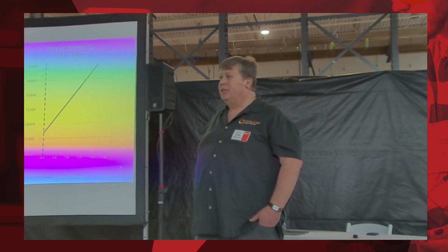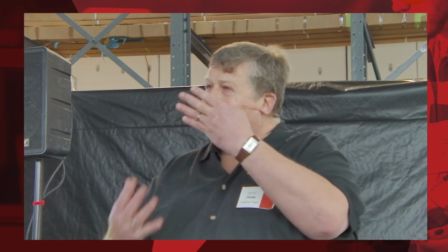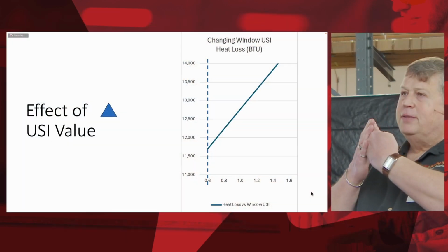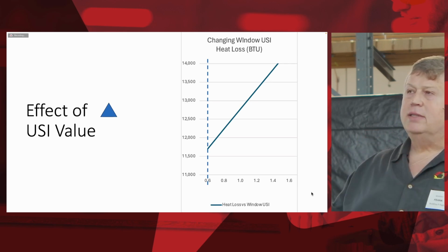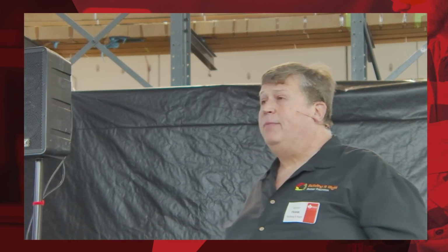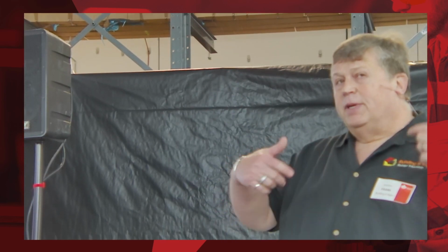But now you got a less efficient device that's using more energy to be less efficient. And you got more mechanicals. You got a little squirrel cage or something running with a desiccant, and it's pulling the moisture before it goes through, or you get a good old HRV. I mean, think about it. It's a bunch of coroplast with the lines this way and this way. And all the air going out goes through the ones in this direction. All the air coming in goes in that direction. And that massive surface contact of those two flows of air is what gives you 60, 70, 80, as much as 85% energy recovery. But if it's forming condensation in there, it's heating everything up. And that's not helping you on the cooling, because you're bringing air inside, and then the condensate actually defeats the cooling or adds to your cooling load.